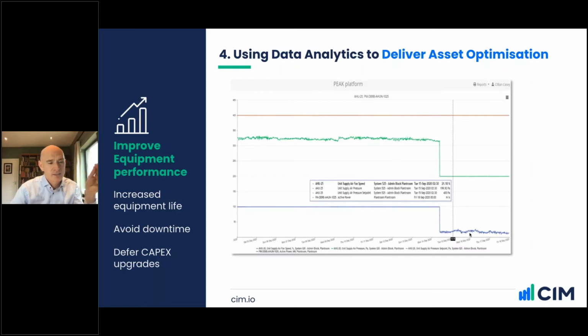And again, it's an example of how the instrumentation in the field can sometimes, and oftentimes, be driving plant and equipment excessively. If you play this out, ultimately, a fan or a VSD running at 100% will fail quicker than one modulating at a lower percentage or a lower hertz.